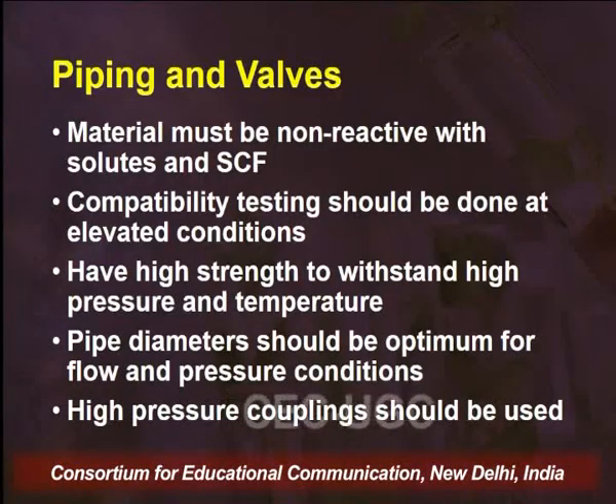And we have seen various pictures of the supercritical fluid unit where we can easily see that various extraction vessels, various vessels that are used in the unit, various storage tanks that are used in the unit, they are all connected by the piping and the valves. And therefore, once you are designing the piping and the valve, the material that you are using for manufacturing these piping and the valve should be non-reactive with the solute and the solvent. The compatibility testing of these piping and the valve materials should be done at the extreme or the elevated conditions of pressure and temperature, because during the extraction, the whole unit is exposed to high pressure and temperature conditions. And once the material is exposed to higher temperature and pressure conditions, through which the solvent is flowing, we know that at these elevated conditions, solvents sometimes become more aggressive in their solubility and their reactivity.